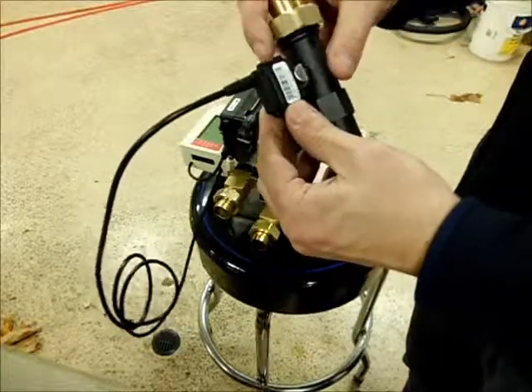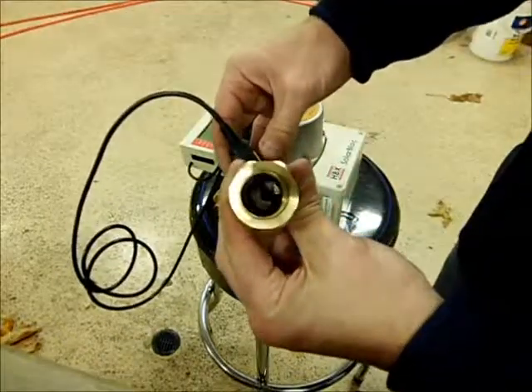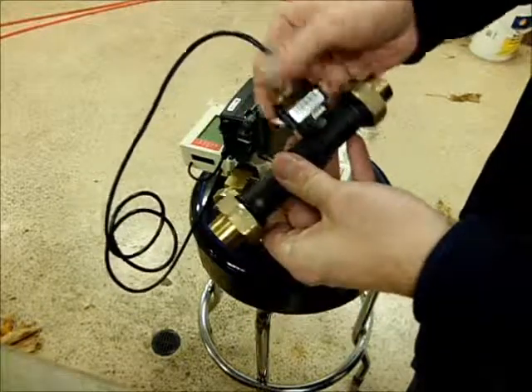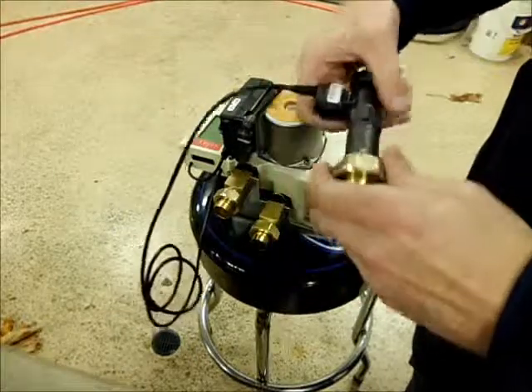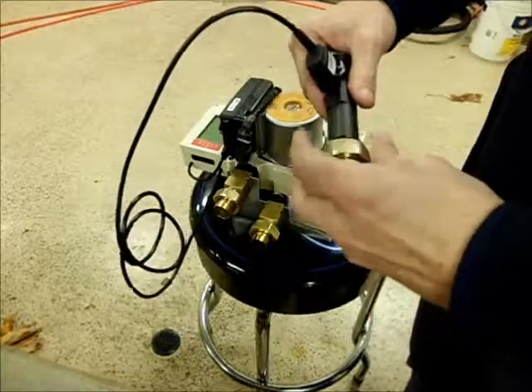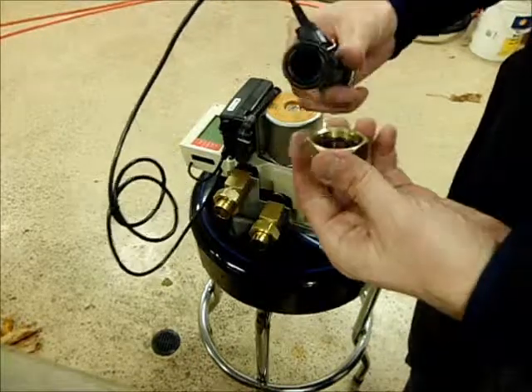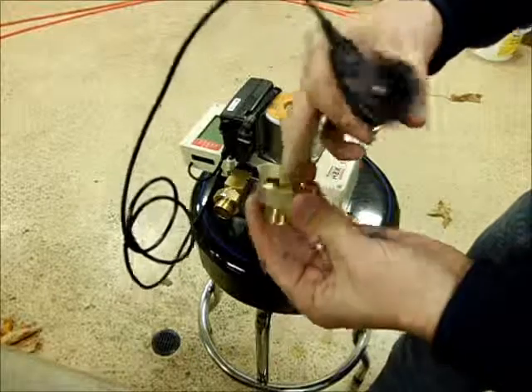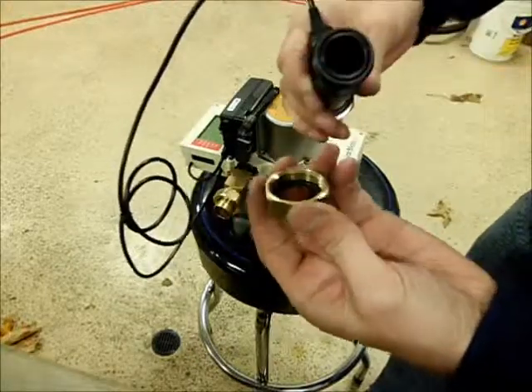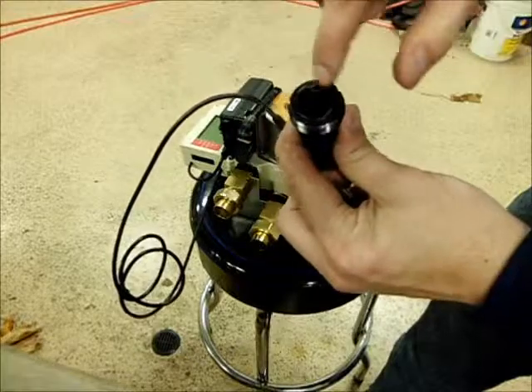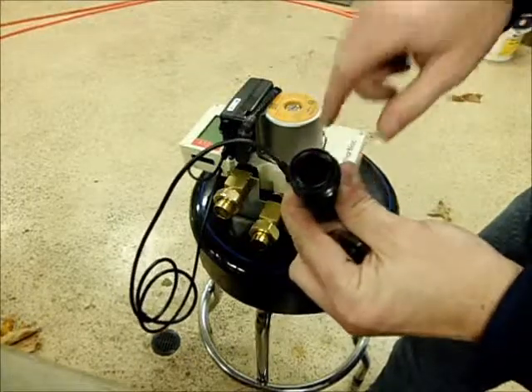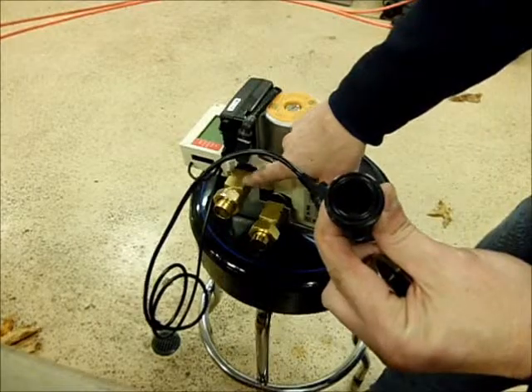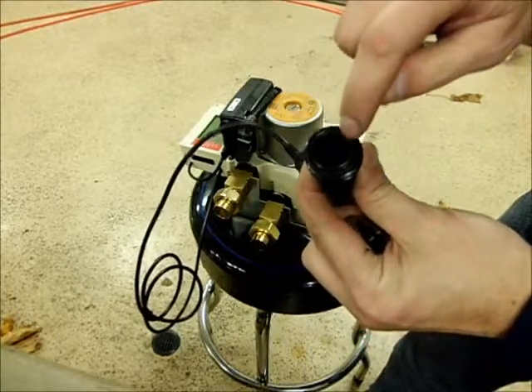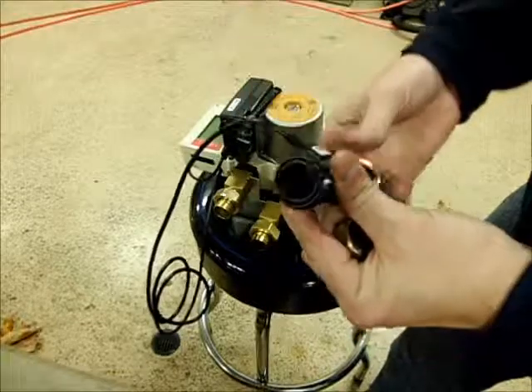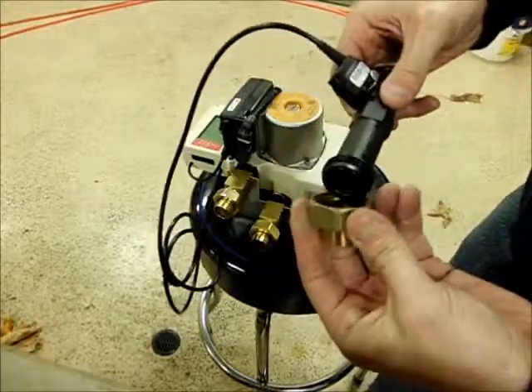This part here, the actual sensor itself that you can see inside the tube, can be removed and replaced. Generally you won't have to touch that. In this case, this one's already mounted. Alright, I'll show you how the fittings go on here. Standard, same way you do your sweat fitting, and you've got your rubber on the inside there. There's 2 O-rings that are larger in diameter than the O-rings that fit in the brass fittings here. So make sure you use the O-rings that are meant for the flow sensor. Just push those in there firm. You can see they barely stick out, but they need to be in there.